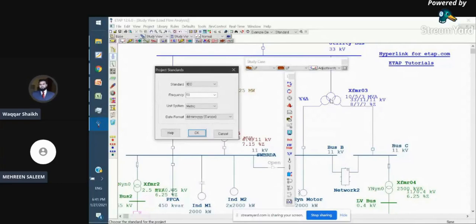Let's take an example of a short circuit study. A short circuit study is done as per IEC 60909. So if we are keeping the standard IEC, by default ETAP will take this option in the software as IEC standard. In all the simulations, it will be considered IEC by default. You can switch this information within the software interface at different places. But if you are sure that you are working on IEC standard, you really don't need to change the options again and again inside the software. Just keep the option in the beginning, right here at this place, and it will be uniform throughout the project simulations and throughout the project engineering works. Changing the standard at a later stage would create some discrepancies, so it's always advisable to pick the right standard in the beginning.